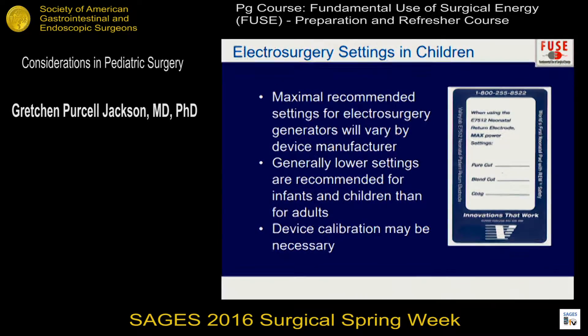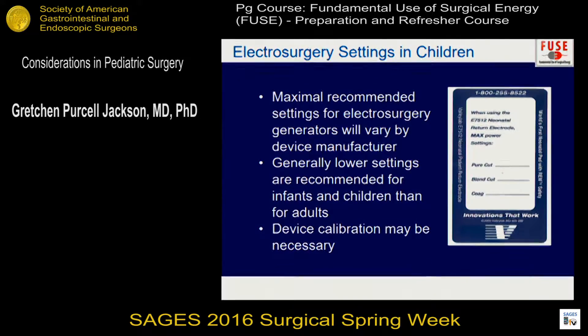If you are using energy devices for infants and children, especially in the under-5-kilogram population, these devices should be calibrated regularly and should have stickers on them — an example being a sticker that tells you the maximal recommended settings for a given patient weight. This may not happen in your operating room, but if you start seeing disturbing effects, this is something worth exploring.